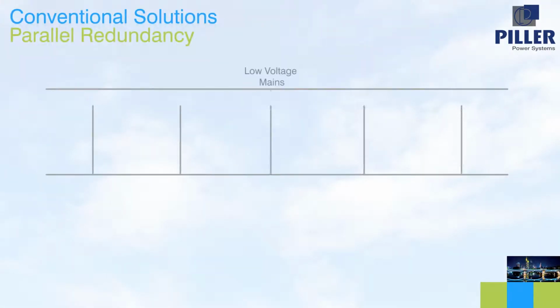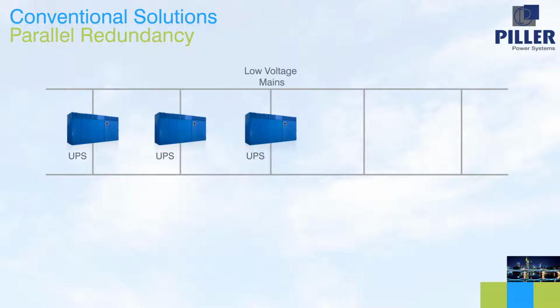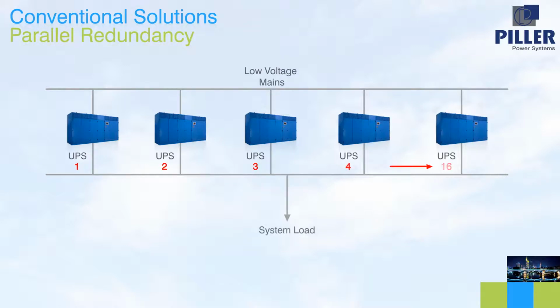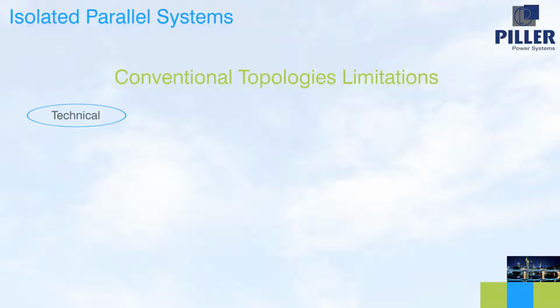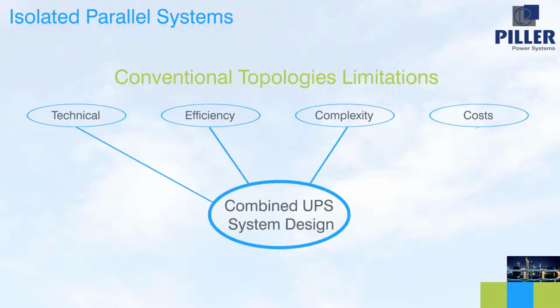A simple parallel scheme where all units are connected via a common bus would seem to meet the main criteria, combining simplicity with optimized efficiency and capital cost. But such a scheme has a single point of failure where the units are paralleled. Consequently, these schemes are neither truly concurrently maintainable nor fault-tolerant. So all conventional topologies have their limitations: technical, efficiency, complexity, cost, or a combination of all four.